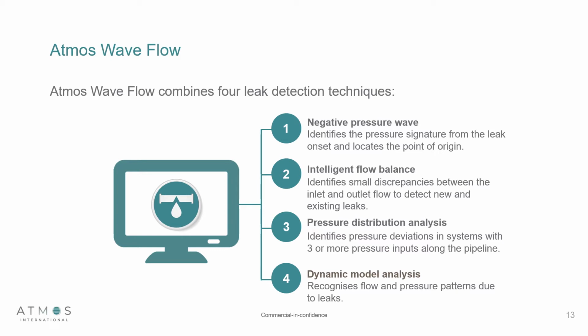As well as those two methods, we combine pressure distribution analysis. If we can have multiple pressure sensors distributed along the pipeline, we can do cross-checking analysis. The advantage of having multiple pressure sensors means we can shorten the distance in which a pressure wave has to travel, and we shorten the distance in which the LDS system has to handle. This means we can have improved reliability, improved response time, improved leak location.